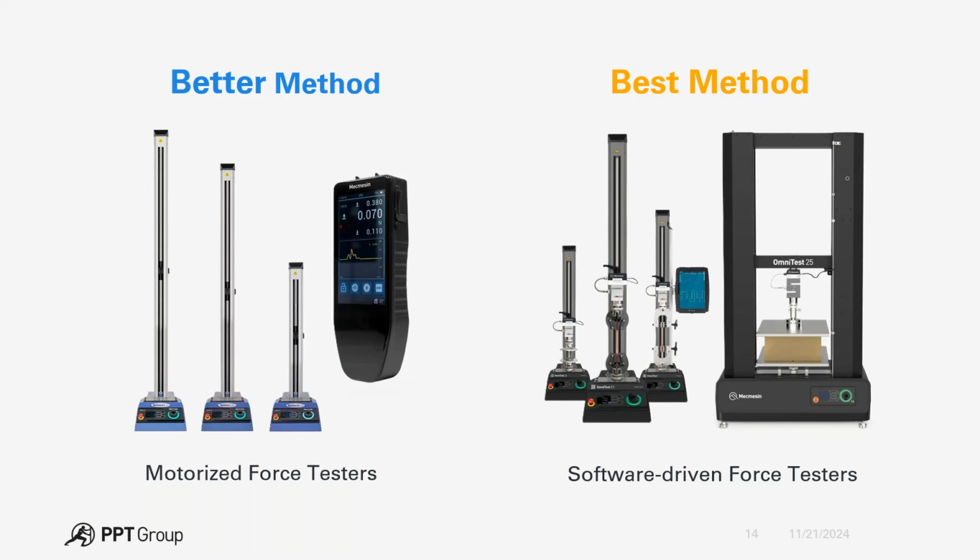So in that case, a good option is using a motorized force tester, attaching that force gauge, which actually measures your compressive force. Now, the advantage of that motorized tester is the two critical factors that users usually would have to guess, which is how fast they're pushing down and how far they need to go, is answered using a motorized tester. So you can program it to run at a known speed of, say, 10 inches per minute and run to that known displacement of, say, 10 millimeters or 6 millimeters or a quarter of an inch. And then obviously that gauge will recognize and register whatever the peak compressive loads are. Now, this is usually good if you're looking to perform the test number one, where you're compressing to a known deflection and then simply measuring whatever the peak load or the top load is.